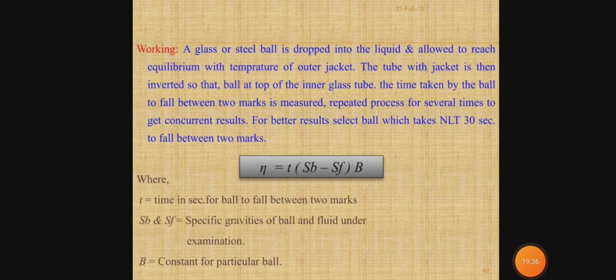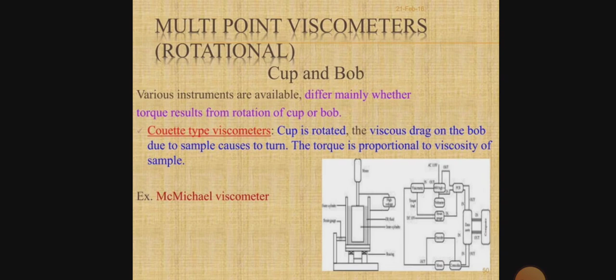Multi-point viscometers: rotational, cup and bob. Various instruments are available. They differ mainly in whether torque results from rotation of the cup or the bob. Couette type viscometers: the cup is rotated. The viscous drag on the bob due to the sample causes it to turn; the torque is proportional to viscosity of sample. Example, MacMichael viscometer. Searle type viscometers: the bob is rotated. The torque resulting from the viscous drag of the system under examination is measured by a spring or sensor in the drive to the bob.